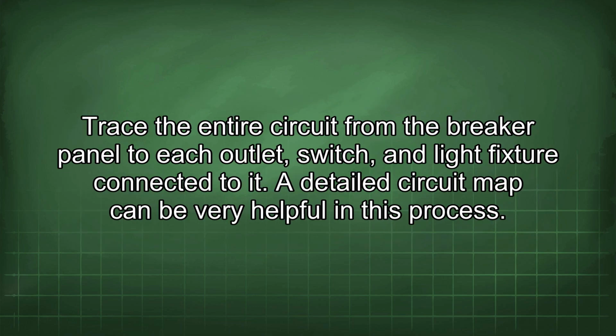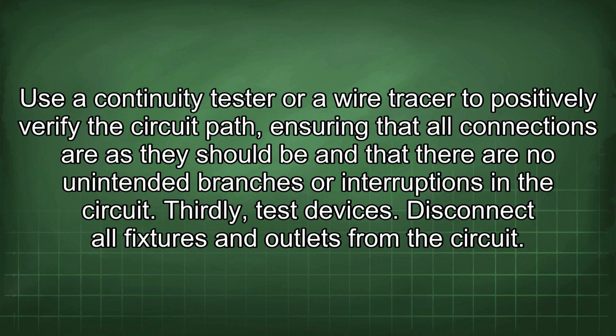Secondly, determine the circuit path. Trace the entire circuit from the breaker panel to each outlet, switch, and light fixture connected to it. A detailed circuit map can be very helpful in this process. Use a continuity tester or a wire tracer to positively verify the circuit path, ensuring that all connections are as they should be and that there are no unintended branches or interruptions in the circuit.